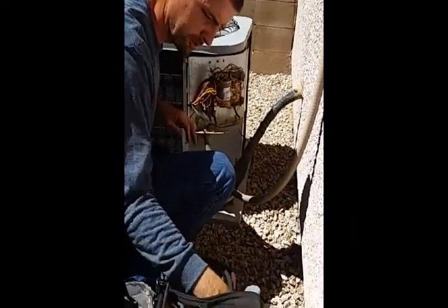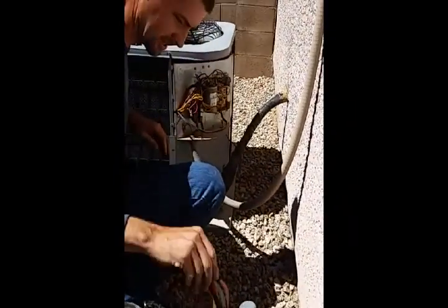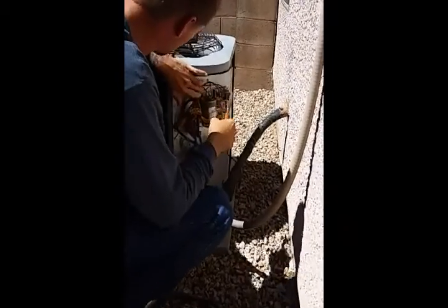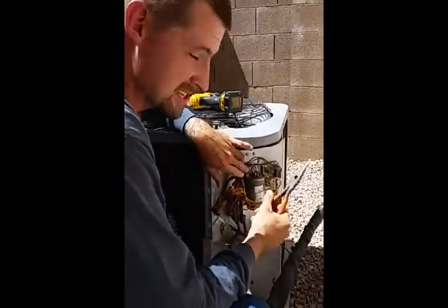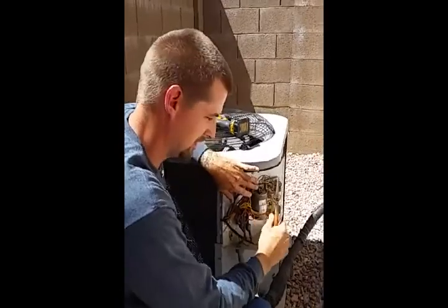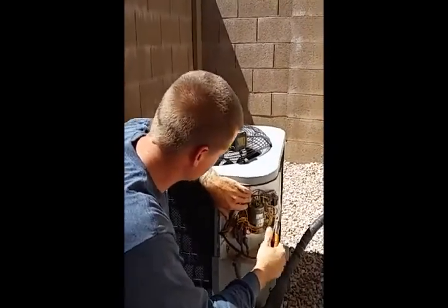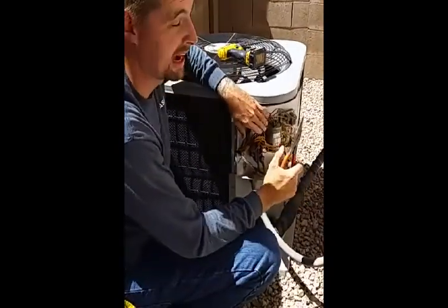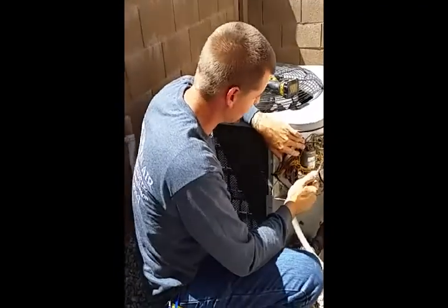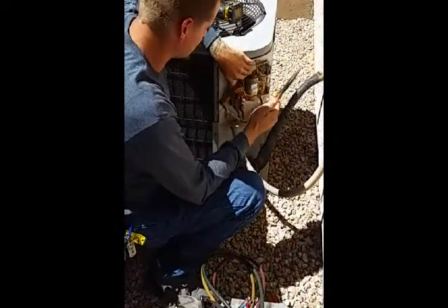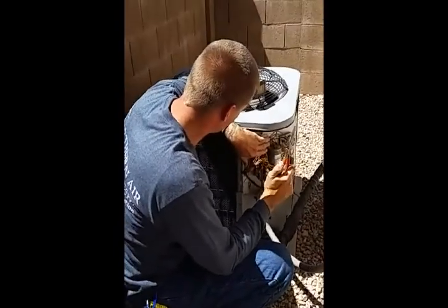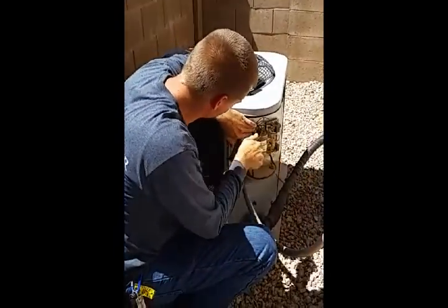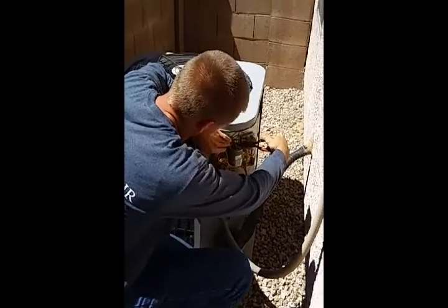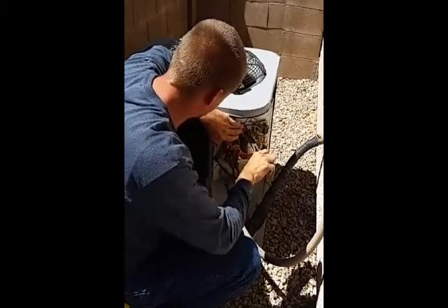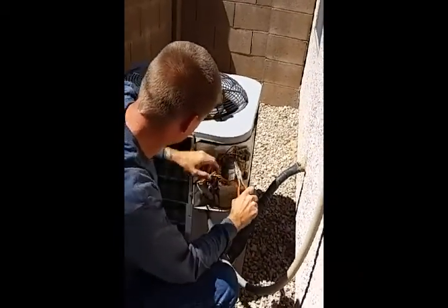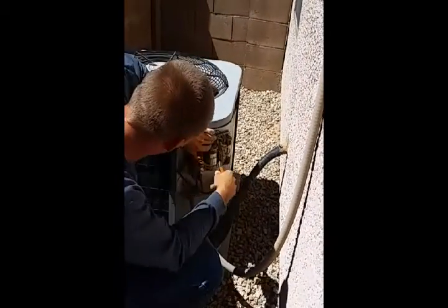Now what I'm going to do is pull the connections off the capacitor and test it. By the way, this isn't the proper way of doing it. You want a bleed resistor of some sort, but make sure that the power is off to your unit, and with an insulated handled screwdriver or pliers of some sort, you can ground out across the terminals. Again, you want some kind of bleed resistor to do it the proper way.